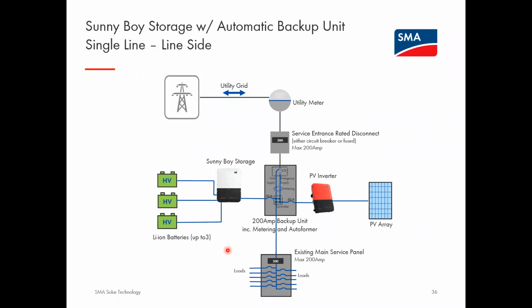Additionally, you don't have to purchase and install a separate sub panel. You don't have to go flipping all the circuits to see what's turning off what inside of the home. That can be rather tedious. So this is definitely a preferred installation method for backing up an entire home, especially if the utility meter is not co-located with the main service.